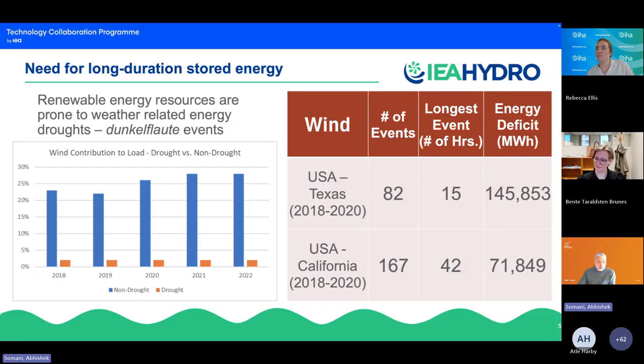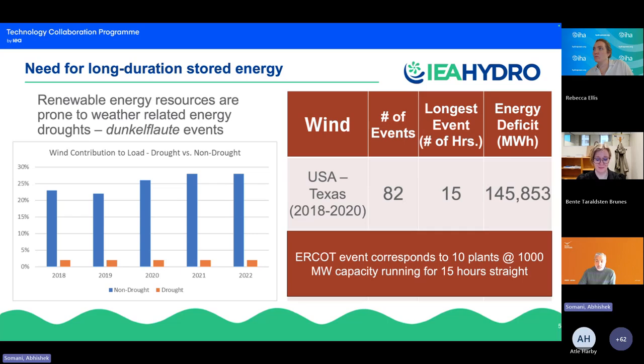If I focus on one specific event, what we call the longest event in Texas, about 15 hours, corresponding to a total energy deficit of about 150,000 megawatt hours. To put this in perspective, this event would require 10 plants of 1,000 megawatt capacity running 15 hours straight—a significant capacity shortfall. Now, we know this happened in the past and the systems were able to ride through these events, nothing untoward came of them. But the question is what happens with more retirements or greater penetration of renewables, which can further exacerbate the situation.